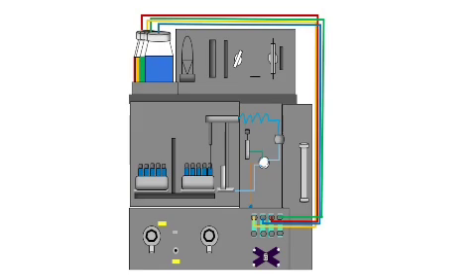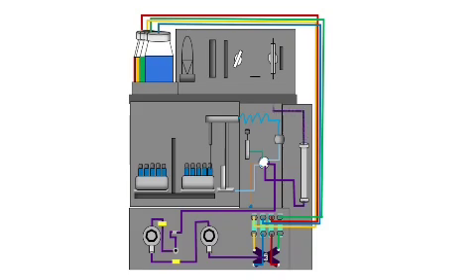In this animation, we are showing a quaternary solvent manager, which is the type of solvent manager on the Alliance system. After degassing, the mobile phases travel through the GPV, gradient proportioning valve, the primary pump, through a transducer, through the accumulator, the other transducer, the prime vent valve, and the inline filter. The mixed solvent then travels to the sample manager, through the injection valve, and through the column, and onto the flow cell of the detector.